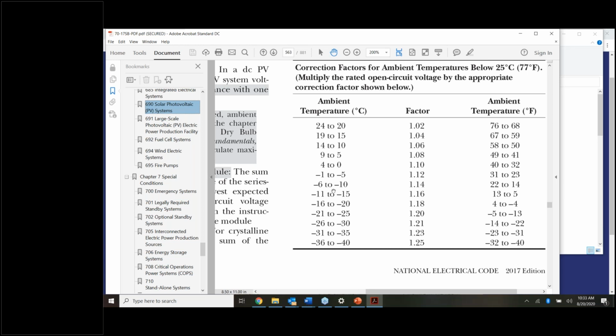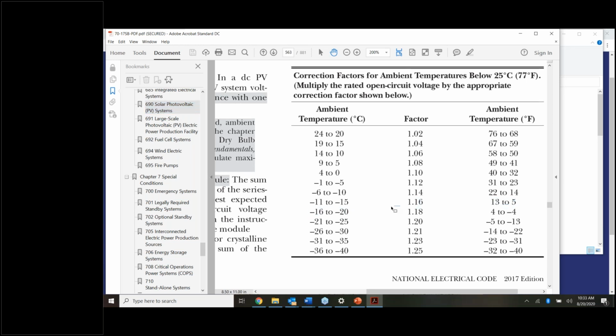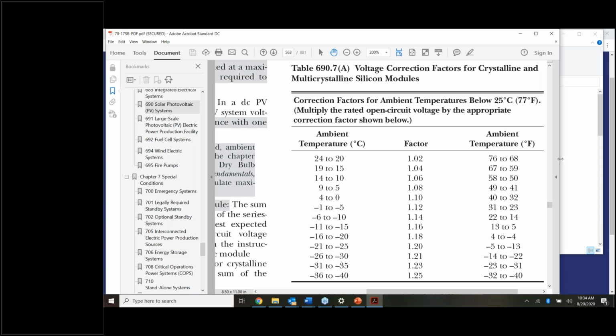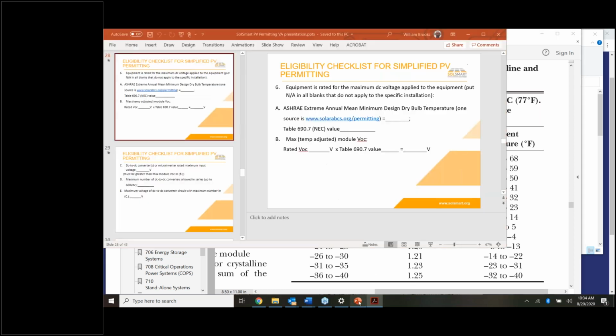Okay, so we said -8, which would be a multiplying factor of 1.14 on this table, to -17, which is 1.18. So that's the range of multipliers if you were to use a multiplier. Now, there are other options. We can actually use coefficients and things like that. But in these simplified guidelines, we're using this table, which is 690.7, the table for crystalline silicon. And this is a very simple table, and these are the multipliers where you increase the rated voltage by this amount, between 14 and 18%, and that gives you your actual voltage. So this is that table 690.7 value.